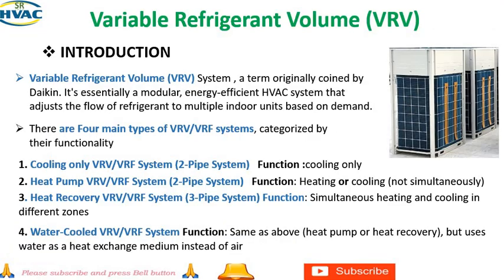So friends, let's start today's Daikin VRV system design. Firstly, what is VRV? VRV stands for Variable Refrigerant Volume. The Variable Refrigerant Volume System, a term originally coined by Daikin in 1982. It designed and developed the VRV system, so it has taken the patent of VRV. It is an essential modular, energy efficient HVAC system that adjusts the flow of refrigerant to multiple indoor units based on the demand. The outdoor unit will supply the refrigerant according to the requirement of each zone or each indoor unit. Formally, there are mainly four types of VRF system categorized by their function.